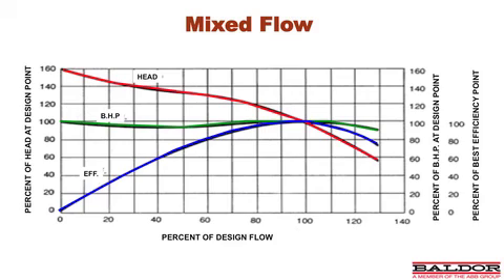Now, what does that look like on the pump curve? Here's a typical mixed flow pump curve. And you can see the red line is your head and flow, the green line is your brake horsepower, and the blue line is your efficiency. And you will note that where the blue line and the red line intersect is the pump's best efficiency point. And you'll note as you move either to the left or the right, your efficiency begins to drop dramatically. You will also note how the brake horsepower rises at shutoff, then drops a little bit, then rises to the best efficiency point, and then begins to drop off as you move to the right of the curve to the runout condition. This is significant. This is why it is so important to maintain best efficiency point of your pumping system.